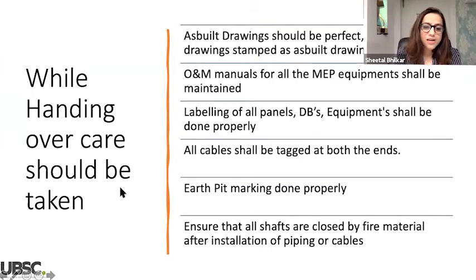And see, as a consultant, we design the building, the work is executed, but at the time of handing over, care should be taken whether the as-built drawings are proper, because from a maintenance point of view you have to see that proper as-built drawings are there. What contractors otherwise do is they just give the working drawings given by consultants and hand them over saying these are the as-built drawings, but it should be checked properly that they are actual as-built drawings, because from a maintenance point of view this plays a very important role. We have seen some sites where we were doing due diligence where proper as-built drawings are not maintained, and then the maintenance team doesn't know how to maintain, where the cables are going, they don't know the routes properly. Even O&M manuals for all MEP equipment should be maintained.